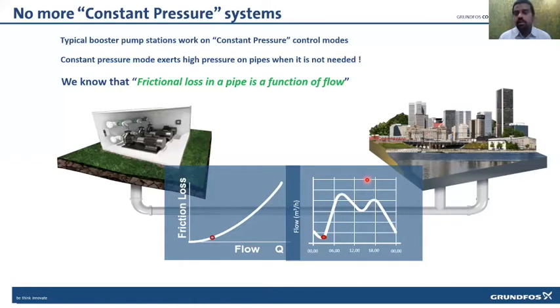Out of these three, static head and terminal pressure are almost static, which is fixed, and will not vary with respect to flow. But frictional loss is something which varies with respect to flow. So we want to take that advantage and see how we can further optimize the energy consumption. It's not only about energy consumption, we say water consumption also.